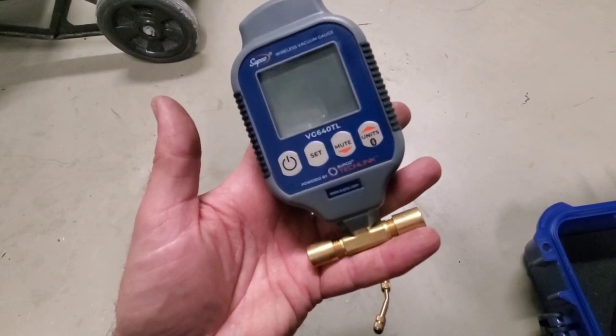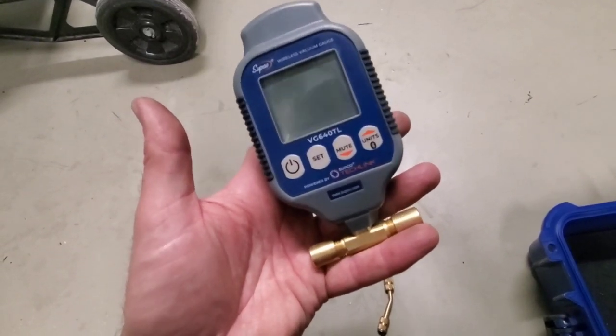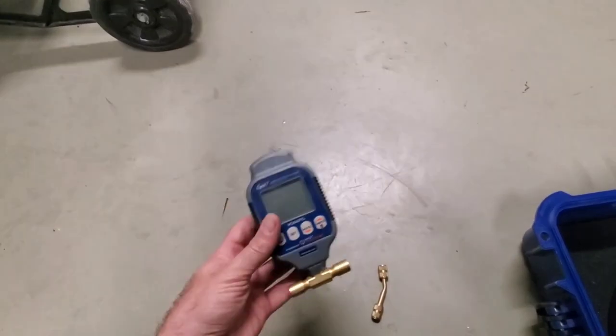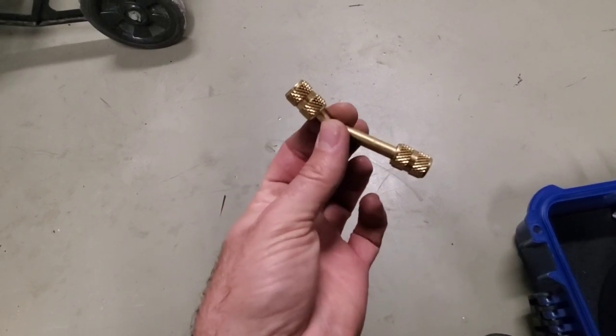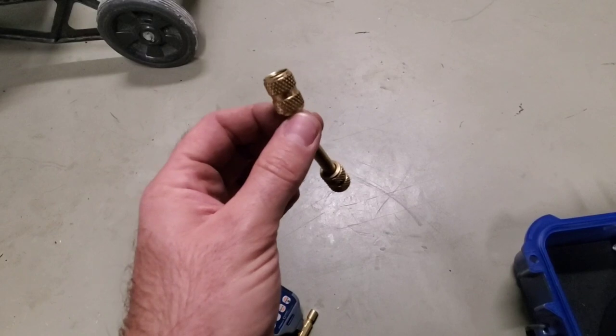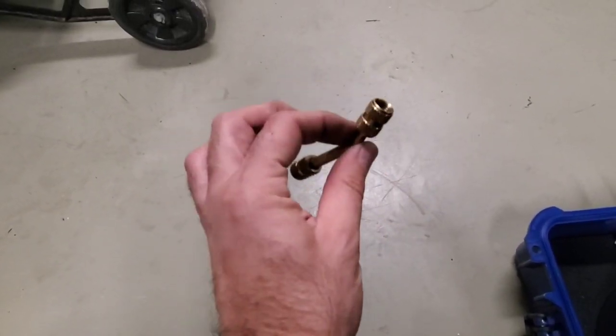In order to pull a proper vacuum, we need to utilize a micron gauge. This is the Supco VG640TL. We use this so we know what pressure the system is at and so we know when the evacuation is finished. For years, industry standard has been around 500 microns, so we want to get below that 100% before we add refrigerant back to the system. We have a coupling on an angle here because we want to keep the micron gauge upright within the system — we don't want any system contaminants getting inside the micron gauge, as they can cause it to read faulty. If we keep it upright, we're going to prevent that from happening.